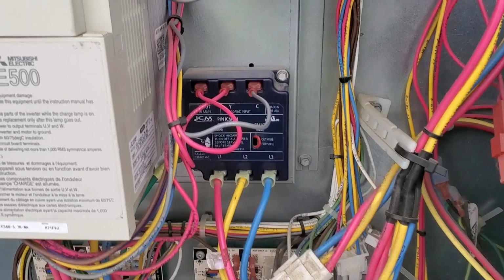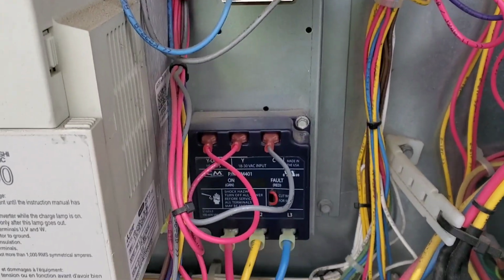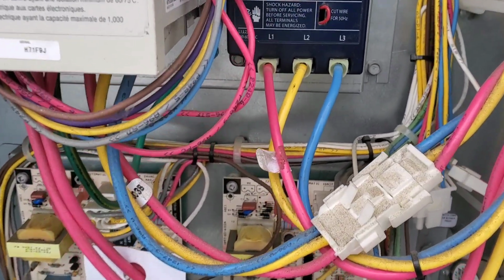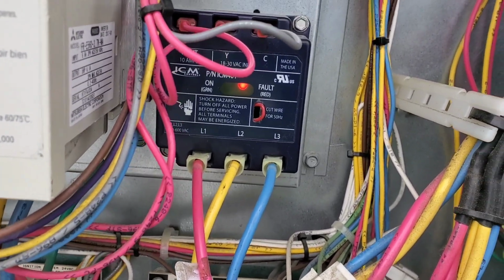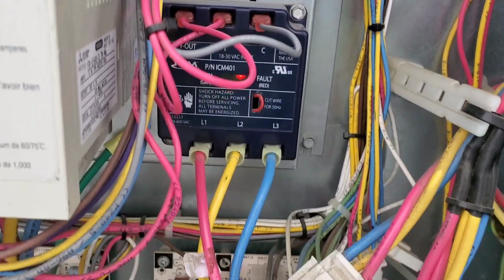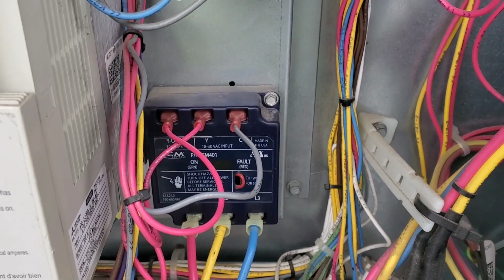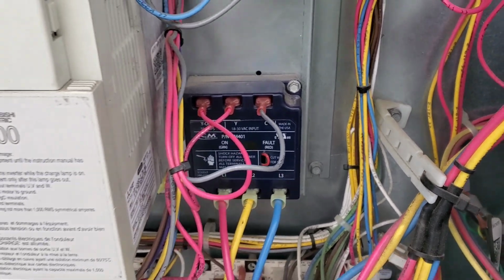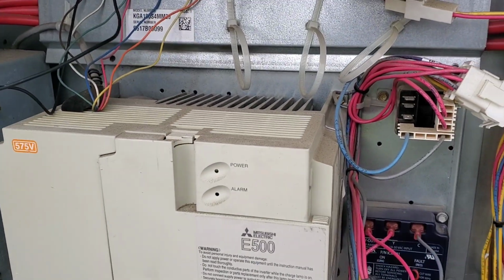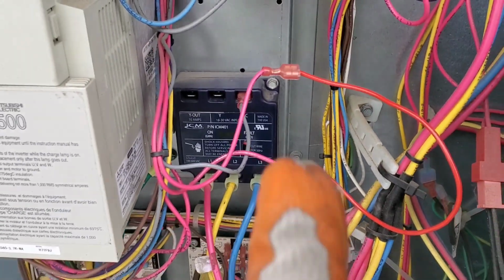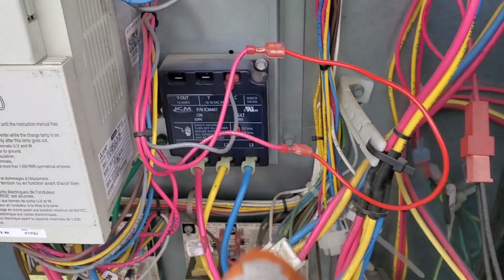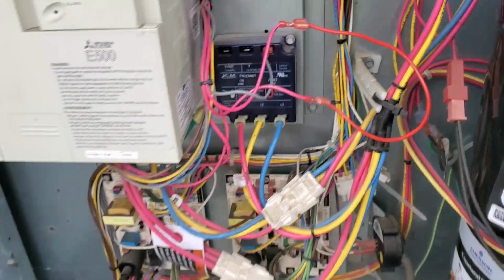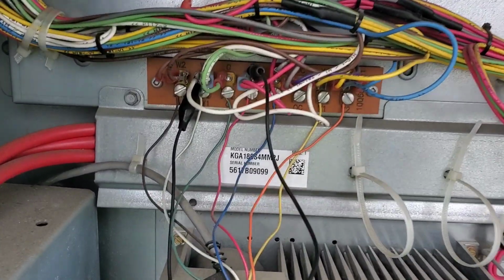Okay, I just wanted to show you I reconnected everything before replacing it or testing it. It is showing a red light. Usually it's green light, so now it's red. That means the device is bad. So we're gonna jump these two wires and test. Already jumped W1, W2. Okay, so I jumped between those two wires. It's a temporary jumper. So let's turn it on. Already jumped R and W1.